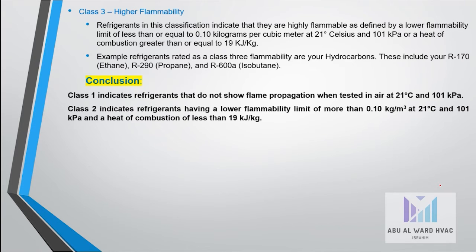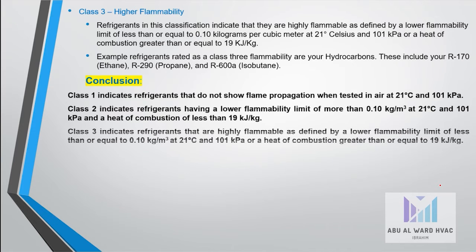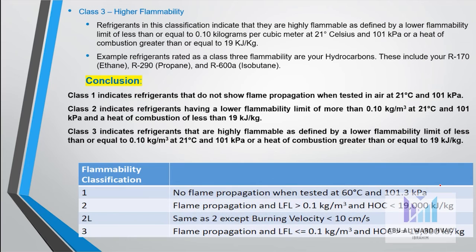In conclusion, class 1 indicates refrigerants that do not show flame propagation, class 2 indicates refrigerants having lower flammability, and class 3 indicates refrigerants that have high flammability. So in total, we have four main flammability classes: 1, 2, 2L, and 3.